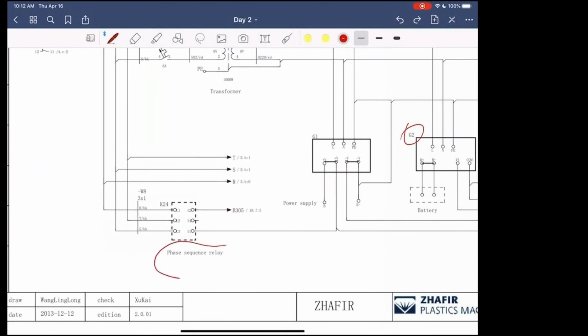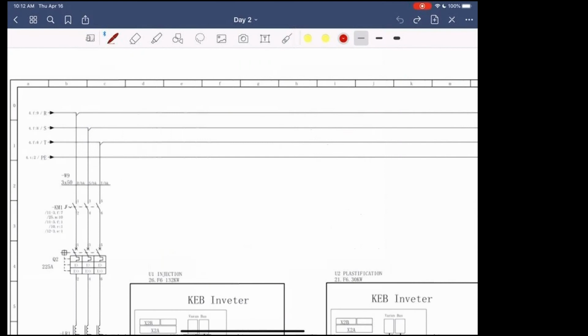This is your phase sequence relay. If you ever hook up the power backwards, that's the thing that's going to tell you, hey, the phases are not right. You also have this going to page 5, which is the next page, and that's going to RST. It's going to be page 5, B1, B1, and B0. Again, you have your cross-reference. It's coming from page 4 F9, page 4 F8, and you have your RST and your ground.